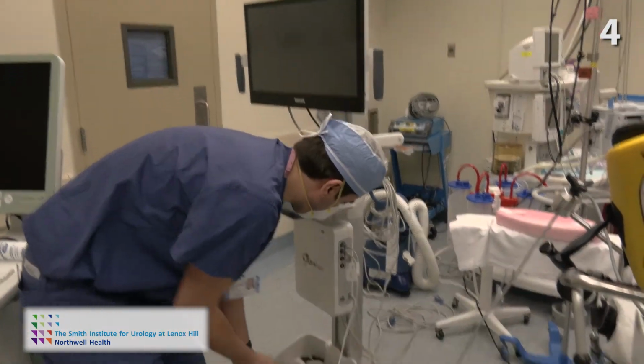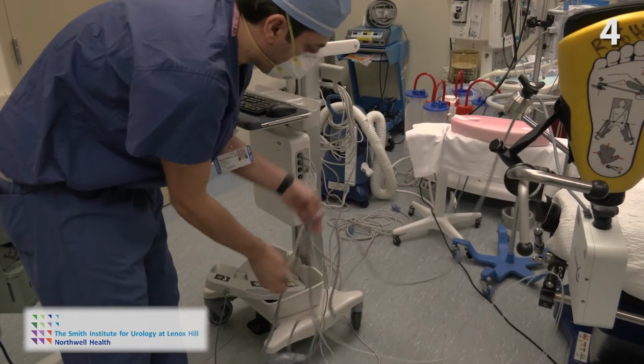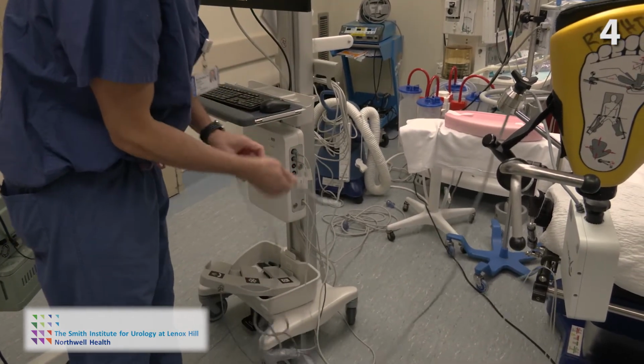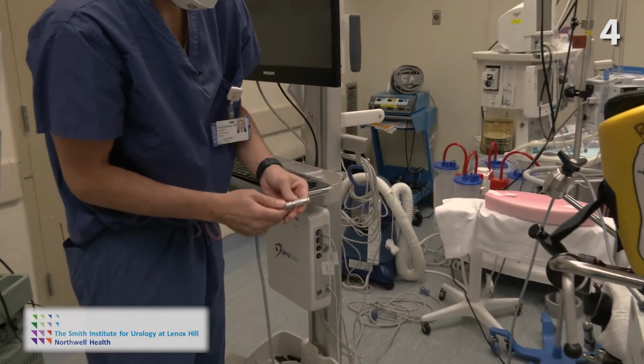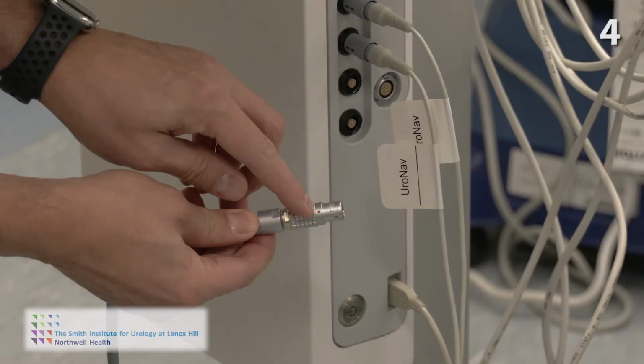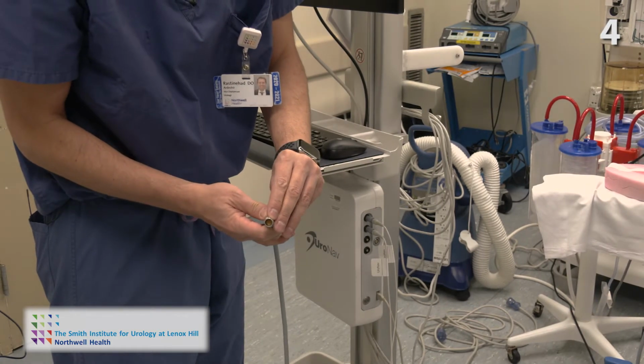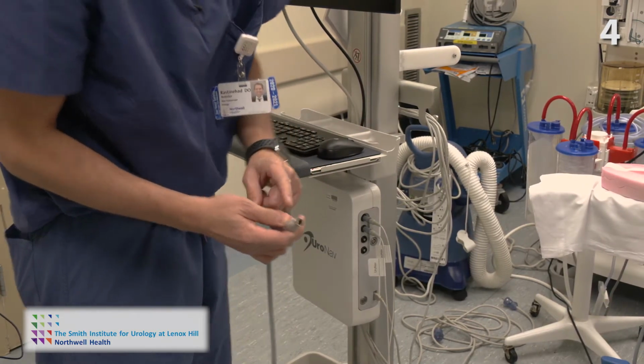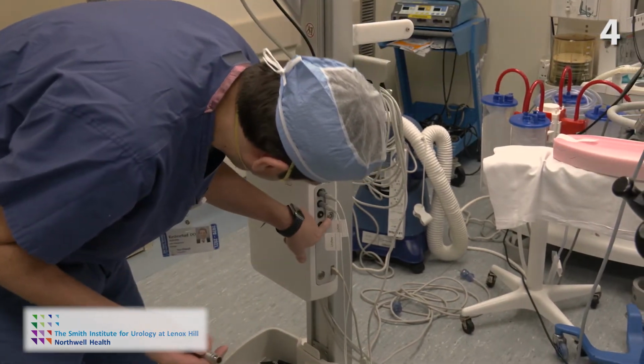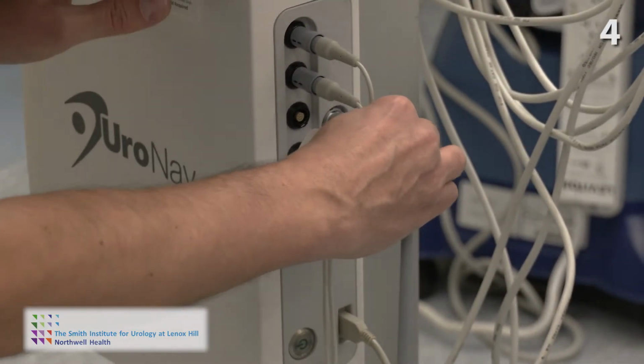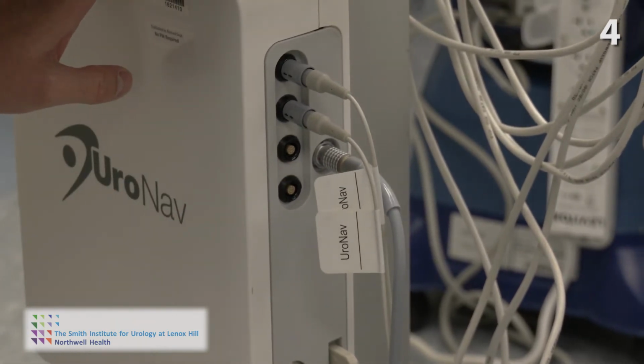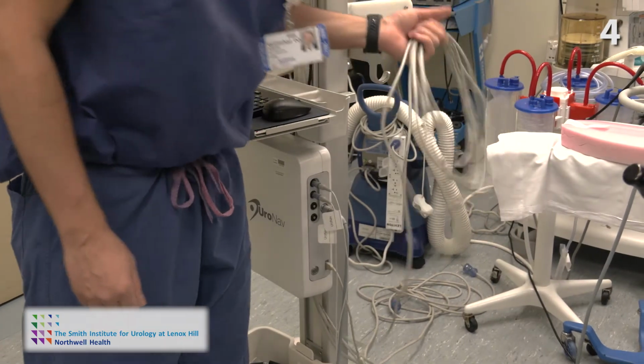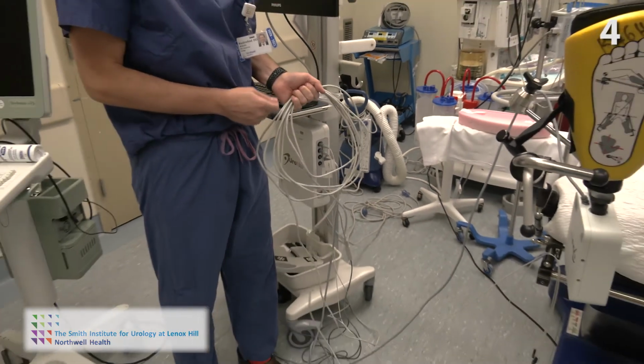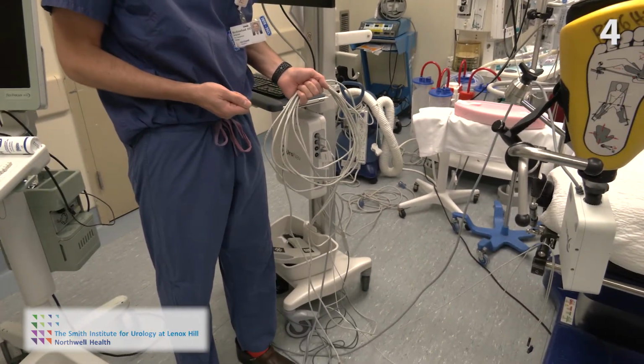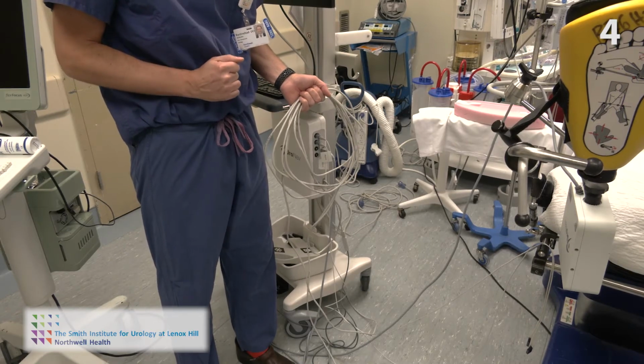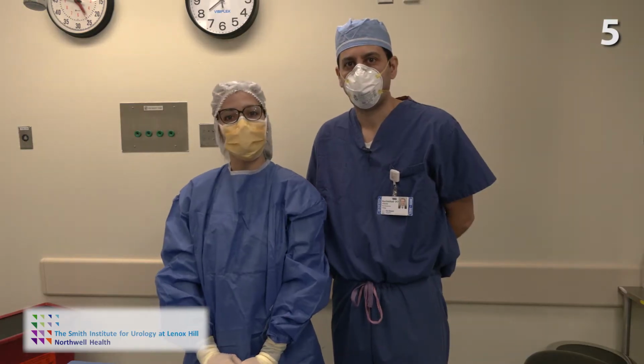The other piece is what we mentioned earlier, which is the most expensive and fragile part of the device, the field generator. The field generator cable is seen here, has a red dot on top to align it. There's small pins inside. If you bend this or force this, you'll break it as well, so please be careful. It goes in right here next to the trackers. All of them point in the same direction towards the front of the device. Finally, all the UroNavs are networked. You must plug this into the corresponding Cat5 jack on the wall to be able to download and upload cases after the case.